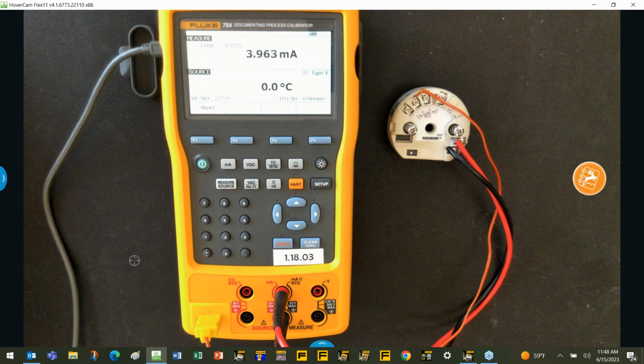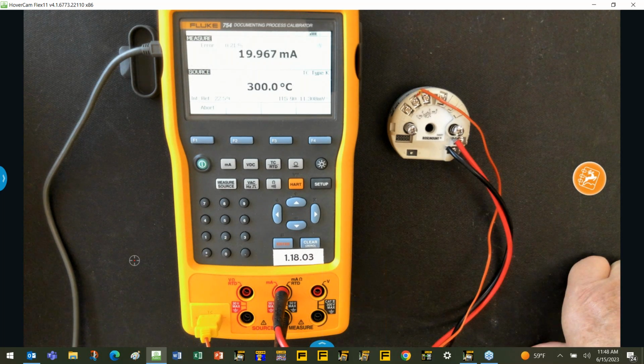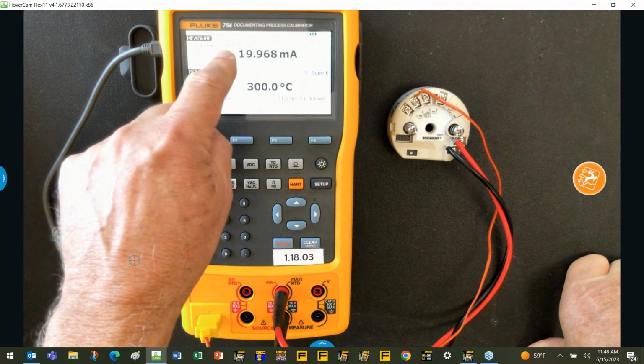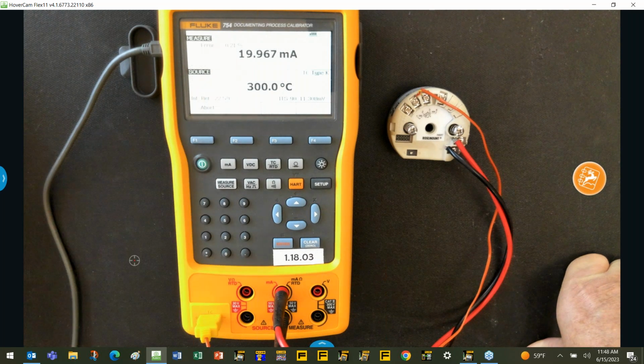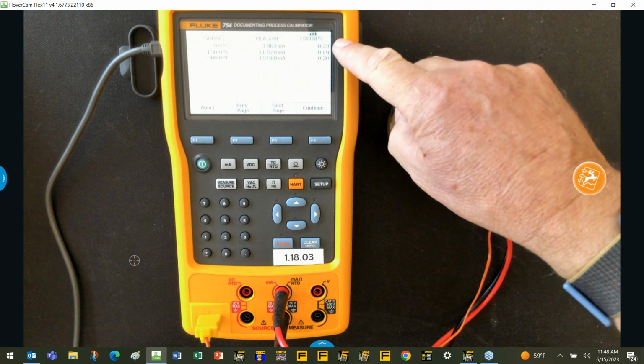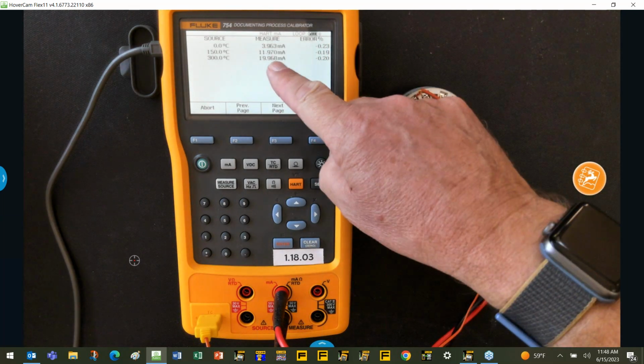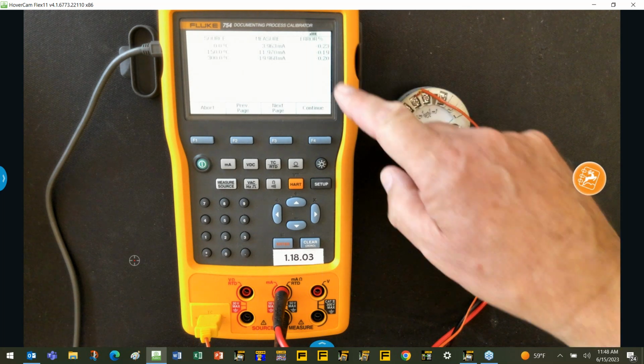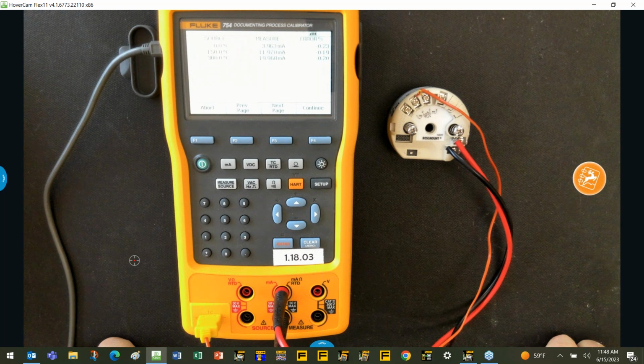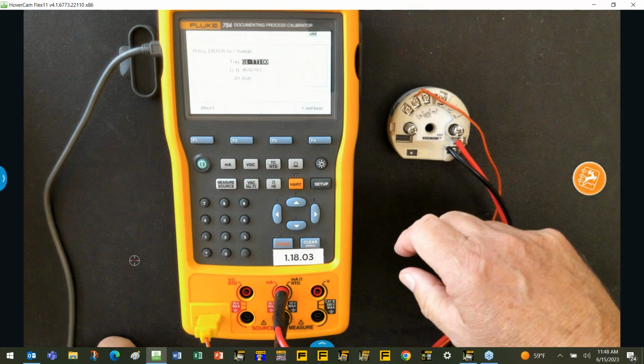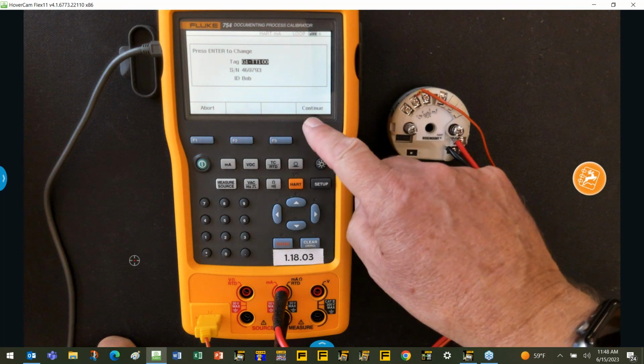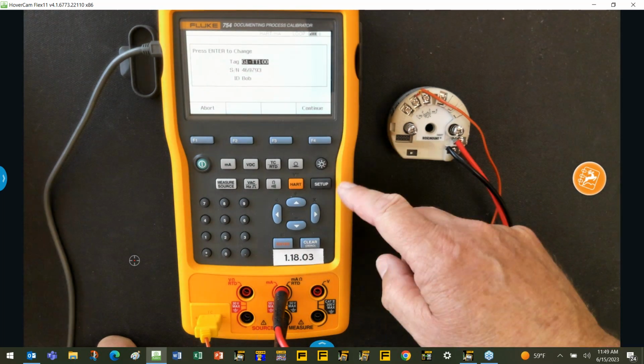So it's going to start at 0 degrees C, get that reading, after a 10-second delay, and then go to 150 at the midpoint. That was the 50% mark. And then when it's got that captured, it's going to go to the 100%, which is 300 degrees C. And you'll notice on top, you'll see the error that it's reading, the error percentage. And so far, it's looking pretty good. So you'll notice in the test result, it's recorded what was sourced, what was measured, and the error percentage. And notice there's no inverse video, so it passed the test. It met that 0.5% accuracy that we were looking for. So press continue. You'll notice it's going to log the tag ID number, the TT100, serial number of this transmitter, and then who did the test, which was me.